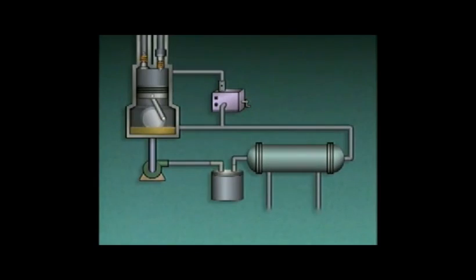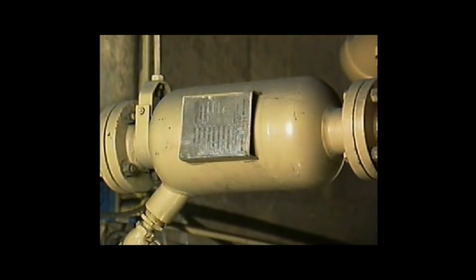Compressed gas systems use auxiliary devices to remove oil or moisture from compressed gas and to prevent overpressurization. Two devices used to remove liquids from compressed gas are oil separators and demisters. Most reciprocating compressors that contain pistons use oil to lubricate the piston rings, and during compression, some of the oil can become mixed in with the gas. This oil must be removed from the gas to prevent system equipment from being damaged, and that removal is accomplished using oil separators.